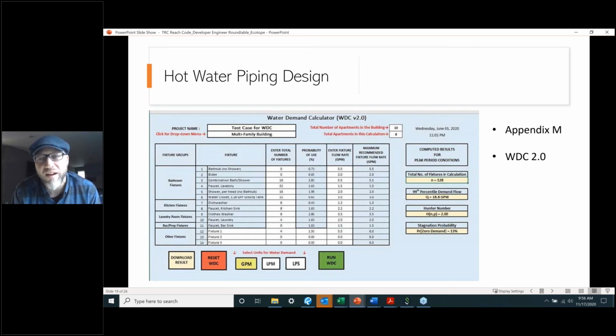California hasn't quite adopted Appendix M. Appendix M is really the alternate sizing approach, which allows you to do right-sizing plumbing design. And then the WDC is the actual tool that helps you design the pipe for the probability of flow. This was based on a bunch of metered data, but based on what we've found, this calculator is almost right on in terms of predicting what the flow would be. So this is another area that'll see a lot more attention and focus, I think, as Title 24 starts to really hone in on some of this stuff.